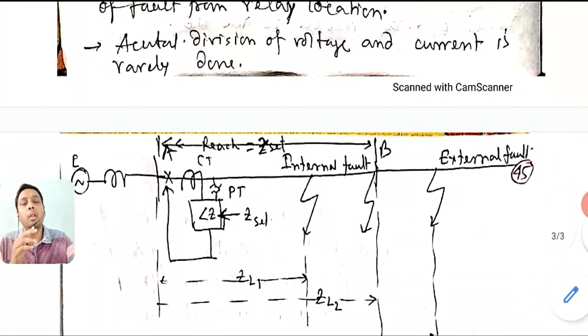Let's see an example, a simple drawing, of how it operates. Suppose there is a CT and a PT sensing this line. Suppose this is the reach, this is the set point which you want to protect. So if there is an internal fault, a fault here, it will get V and I, and V will be I into this Z. So what do you think? V by I, this Z will be less than your Z set.